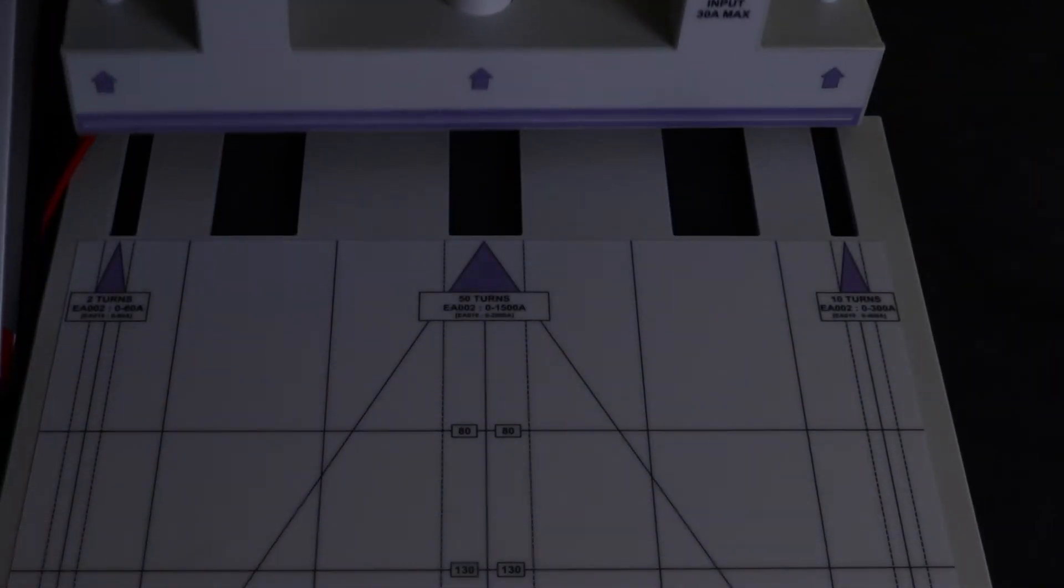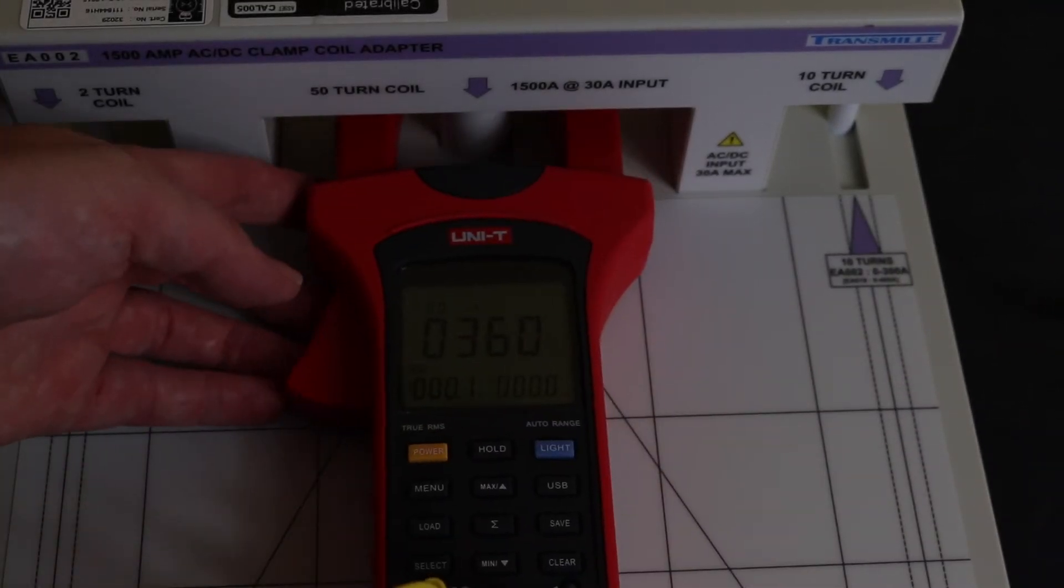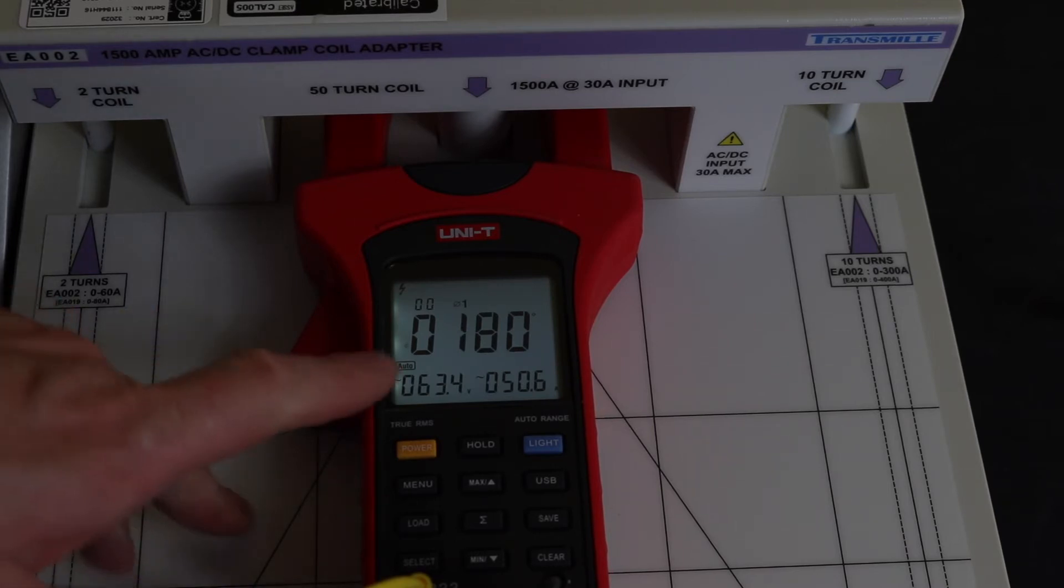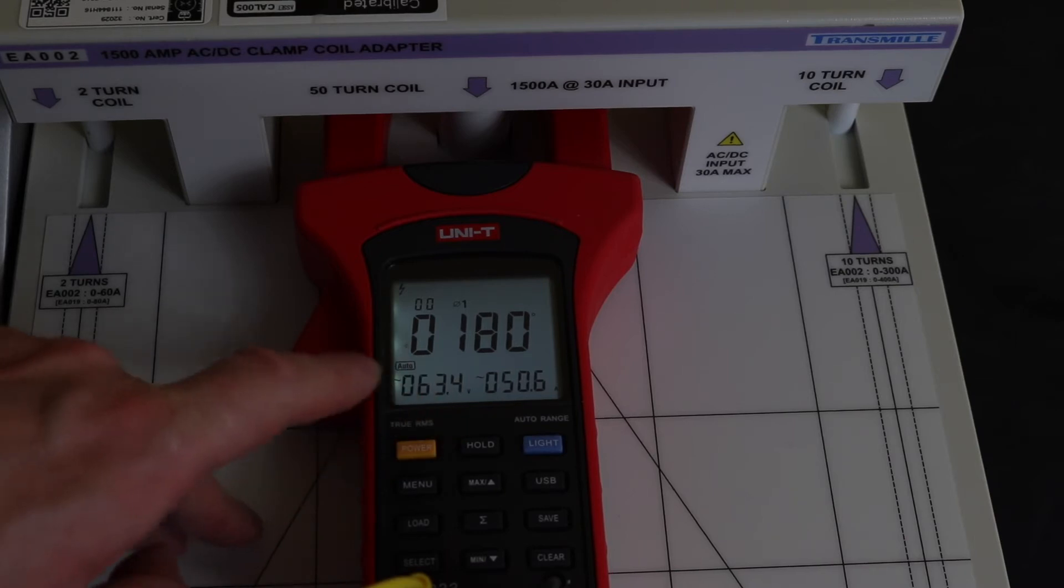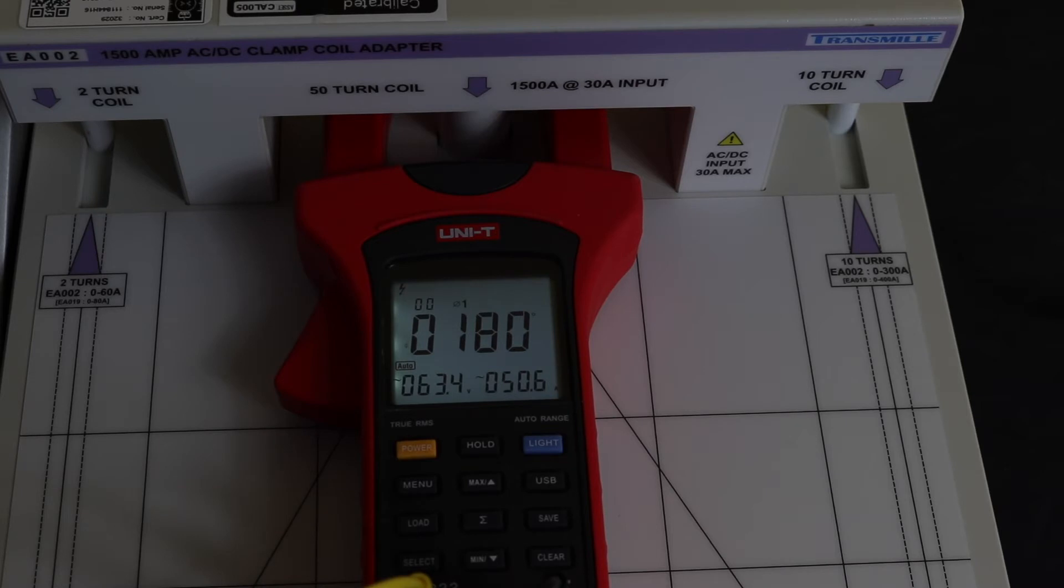we've injected on the first stage - that's 63 volts, 50 amps. But you can see the degrees is at 180 degrees, which is wrong because this should be zero degrees.